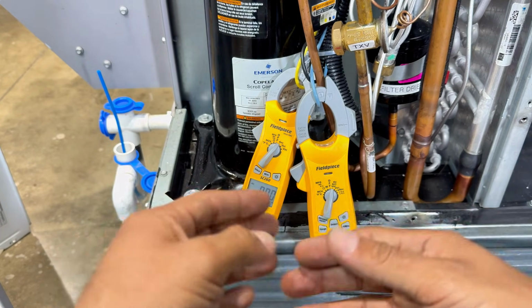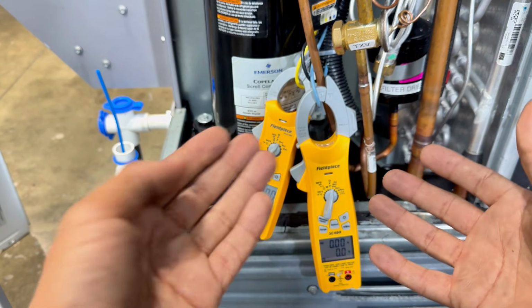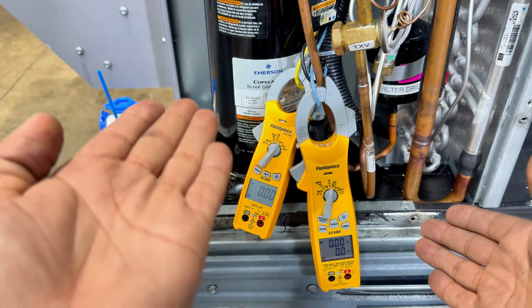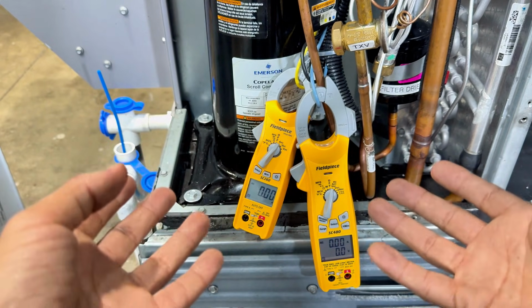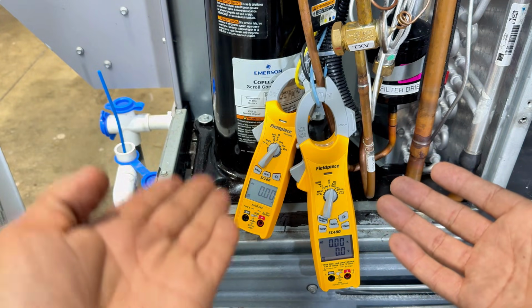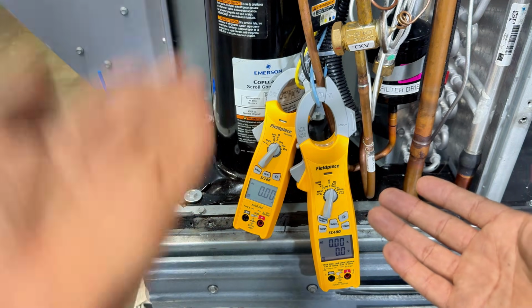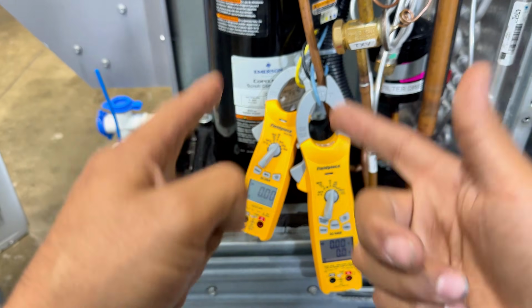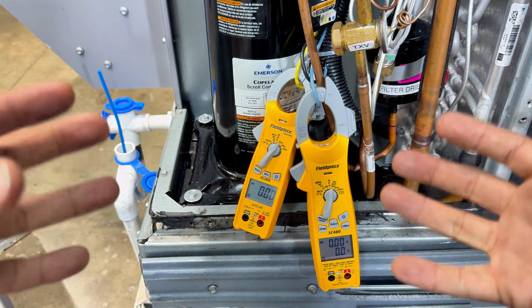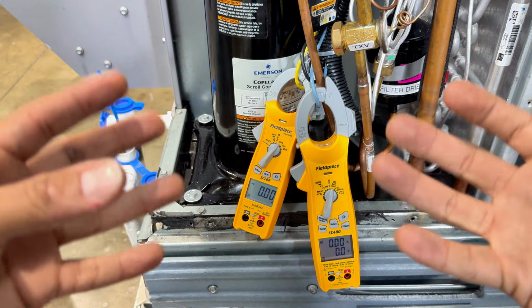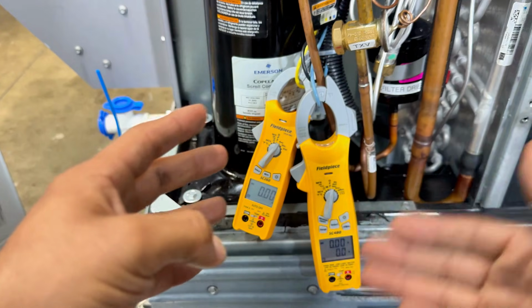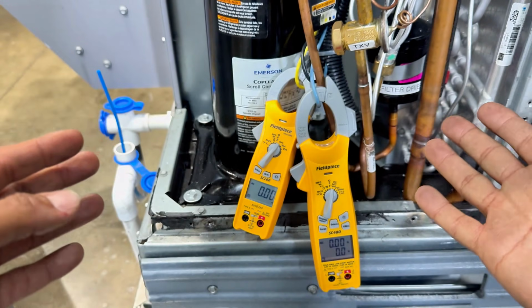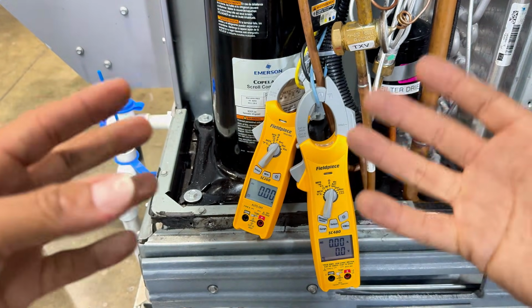But let's say when we just turn it on, which we're going to do right now, let's say it goes up to like 15 or 20, and then it comes down to 4. That makes sense. But what if it goes to 100 or 120 amps and then it drops down to 4? Something's going on. Why is it needing that much inrush current, saturated current, to get going if my capacitor is good? So that's just another indication of what's going on with the compressor.